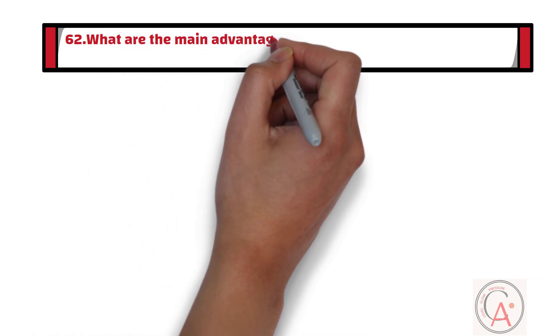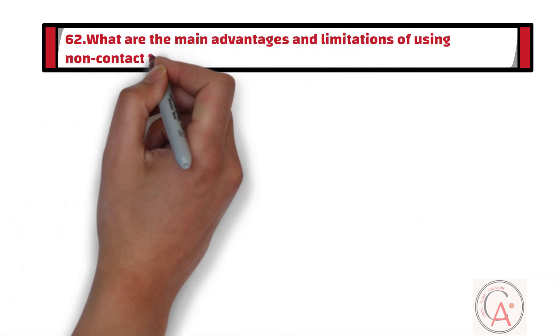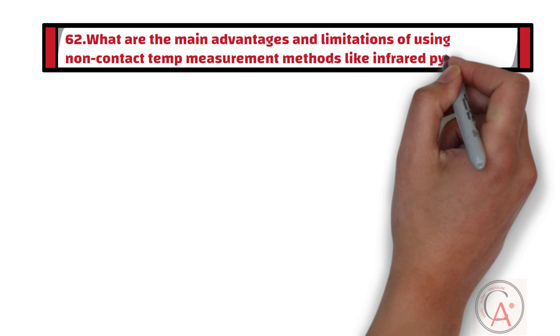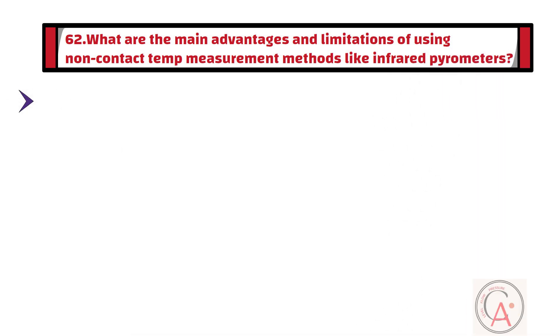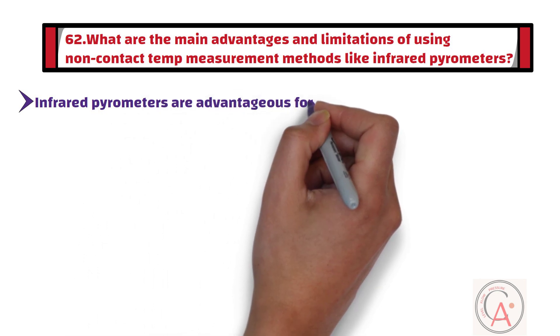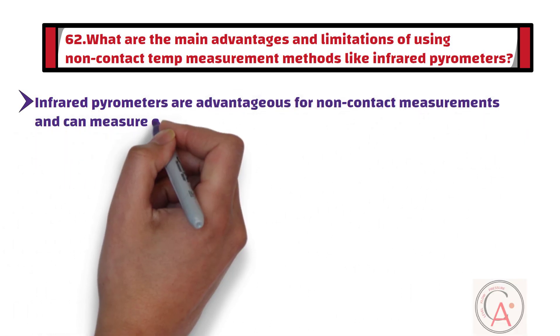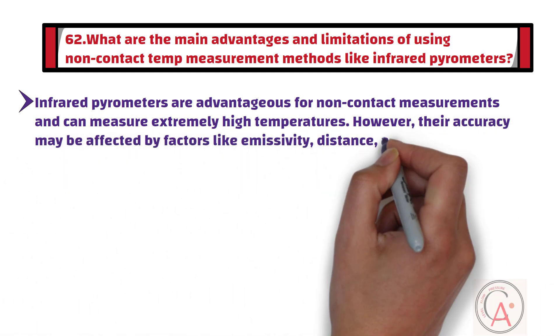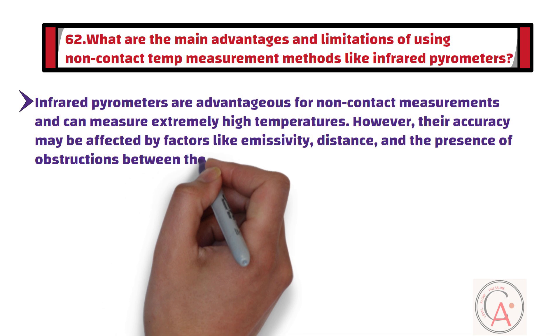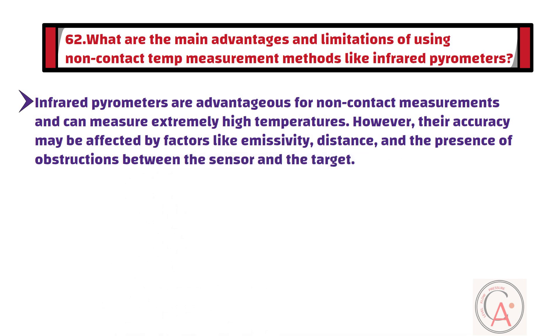Question number 62: What are the main advantages and limitations of using non-contact temperature measurement methods like infrared pyrometers? Infrared pyrometers are advantageous for non-contact measurements and can measure extremely high temperatures. However, their accuracy may be affected by factors like emissivity, distance, and the presence of obstructions between the sensor and the target.